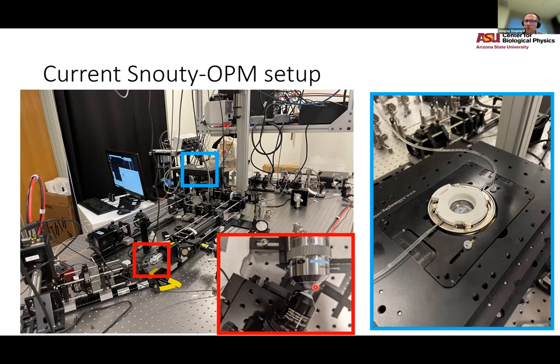In our case, 30 degrees is about the critical angle for our microscope objective. It's just under it, which means that's the steepest we can bring a laser beam out without having total internal reflection occur. So we went for that, which gives us the highest resolution, but the shallowest Z depth. Other groups have argued that the thing they're interested in is further off the coverslip, so they don't tilt it as much, and they shoot the laser beam at a different angle up into the sample. Really it's determined by your use case, and ultimately by the optics. You can't go steeper than the maximum alpha that I discussed that determines the resolution. You can't come in steeper than that.